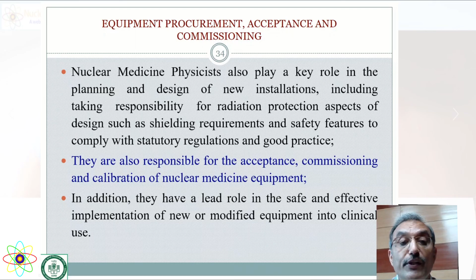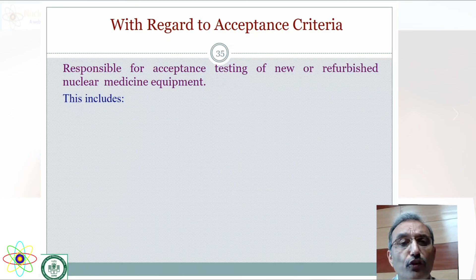They are also responsible for acceptance, commissioning and calibration of nuclear medicine equipment. In addition, they have a lead role in the safe and effective implementation of new or modified equipment into clinical use. As far as acceptance criteria is concerned, they are responsible for acceptance testing of new or refurbished nuclear medicine equipment. It includes safety testing, stability testing, performance acceptance testing against national standards and against selection and supplier specification, establishing basic machine performance quality control baselines.